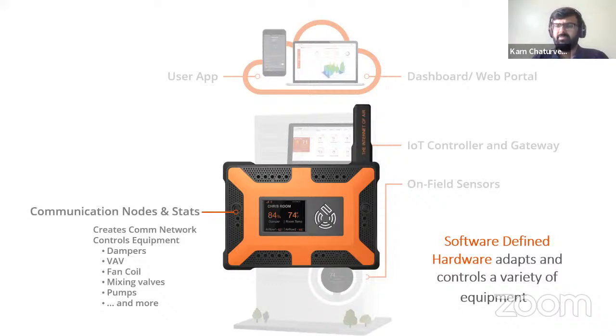So for controlling some dampers, some valves, or running simple PI loops, it can be done, because the IO points for simple devices are all very similar. It's just that the type of device dictates the control sequence. So you can utilize similar IO points to control various types of devices, and all you have to do is swap the control logic. So this would be the other component - a communication device along with a simple controller.